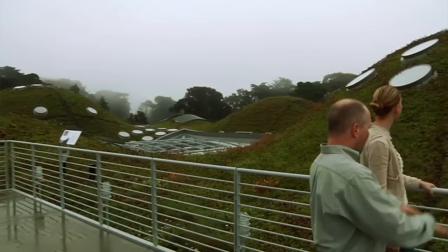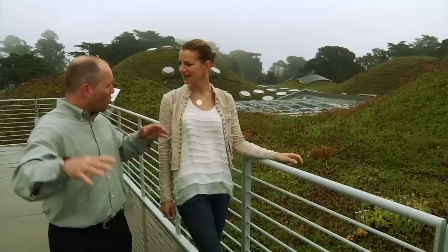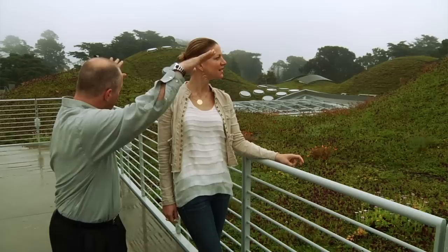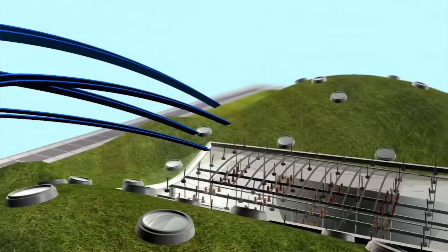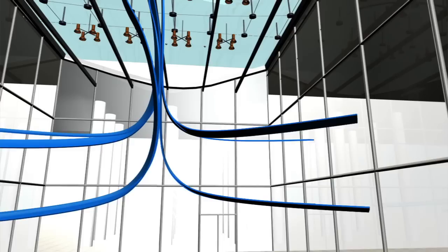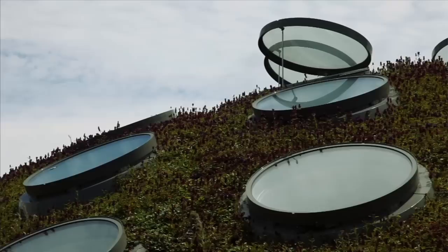This is the rainforest dome and behind us there is the planetarium dome. You'll see there's two equal sized domes on the roof. These domes are actually a really important part of the passive cooling system for the building as well. Cold air sweeps across the roof, goes across these domes on the hills, and channels down into the piazza which is right behind us. Although the piazza looks like it's closed from the outside elements, there's actually a perimeter gap all the way around it — it was designed purposely to be an outdoor space. The cold air sinks into the piazza, and then we have windows at the base of the piazza which we can open up. That sucks the cold air into the building's interior spaces and provides passive air conditioning. The hot air rises and is vented out through these skylights here in the dome. So we have this circulating cooling effect which saves us a ton of energy and a ton of money.